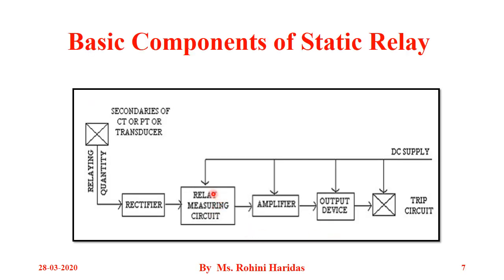In this diagram, you can see the output of the rectifier is applied to the relay measuring circuit. In conventional electromagnetic relays, the measurement is carried out by comparing the operating torque with the restraining torque. The electromechanical relay operates when the operating torque exceeds the restraining torque, and the pickup value is obtained by the movement of the movable element. But in the case of static relays, the measurements are performed by static circuits — we use comparators, level detectors, etc., to compare the input quantity with the preset value.